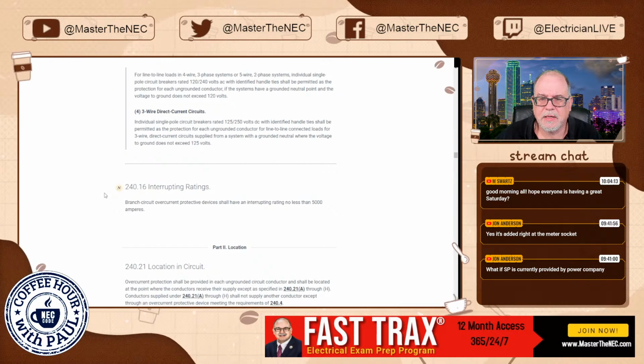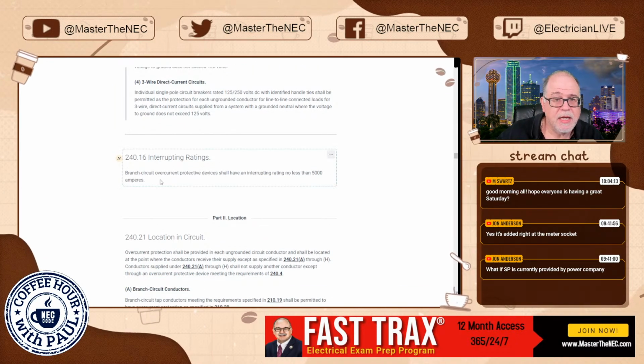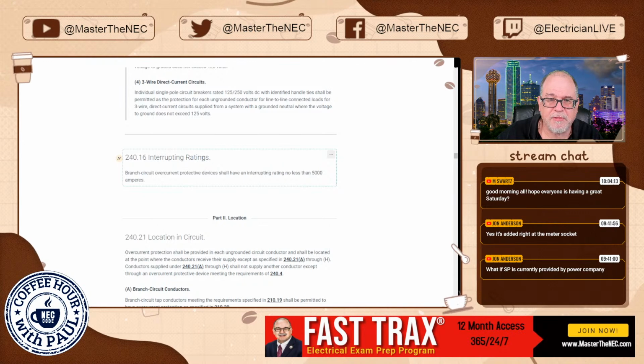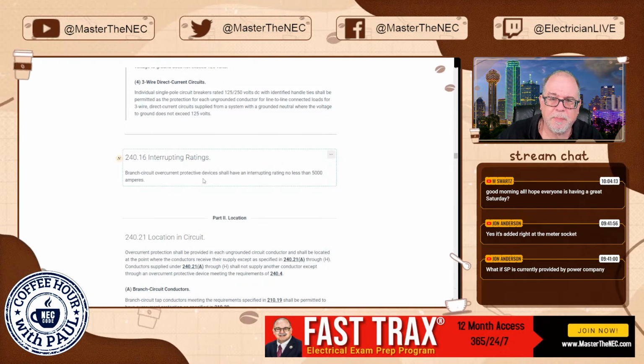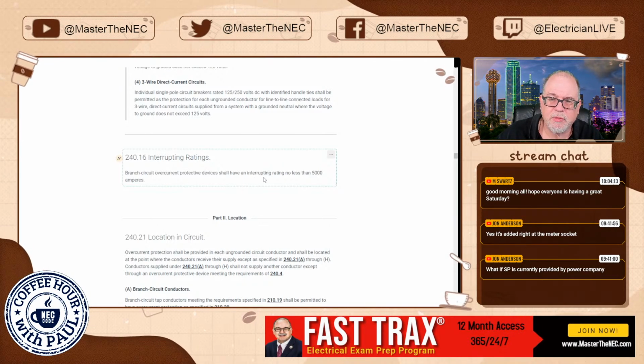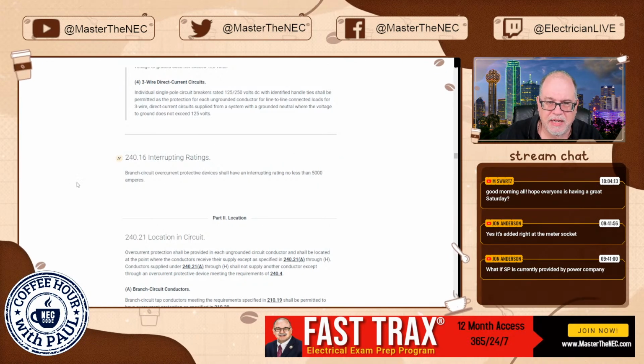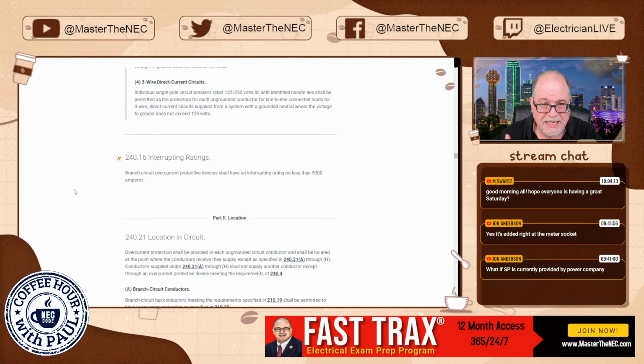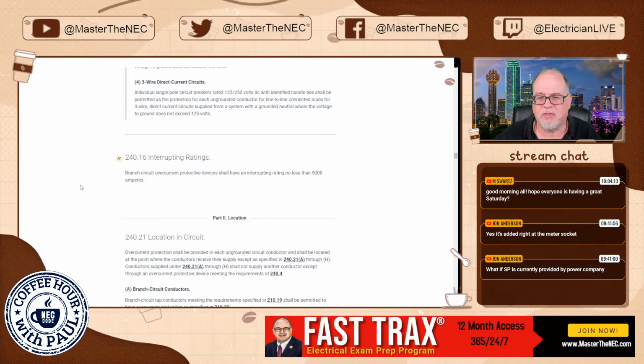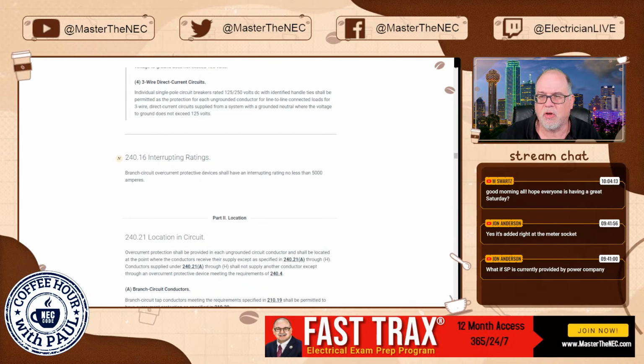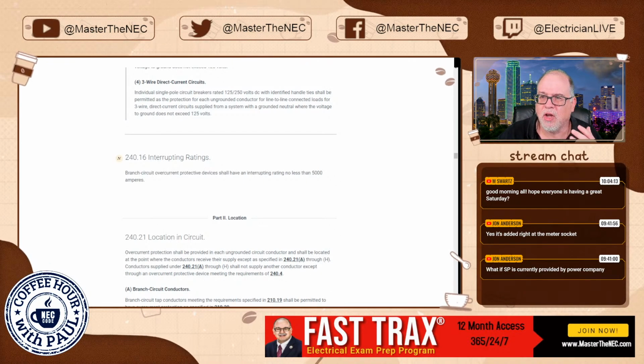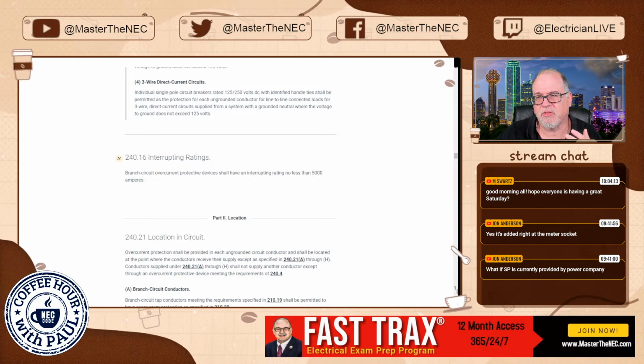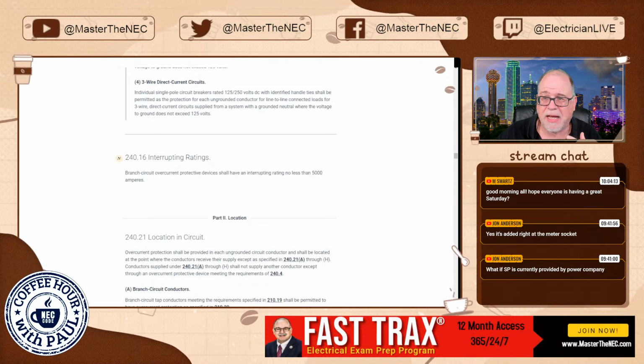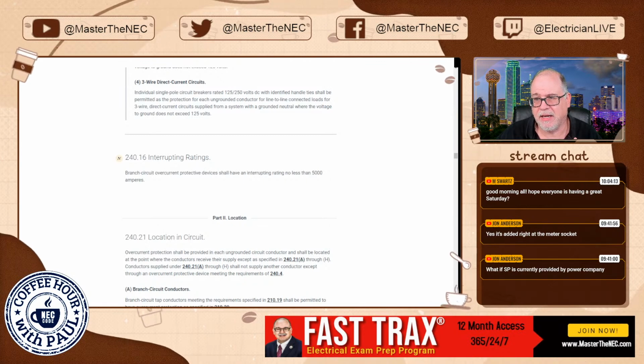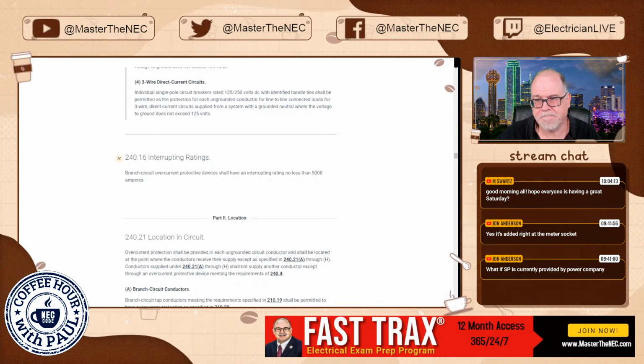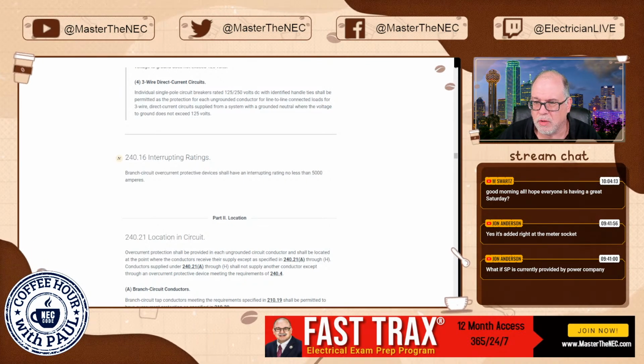Let's see. All right, 240.16, interruptive ratings, says branch circuit overcurrent protected devices shall have an interruptive rating not less than 5,000 amperes. Now, this was already in the code, but now it has been separated out so that it stands on its own. Okay, so there's no question about it, anything like that. So the interruptive rating, right?